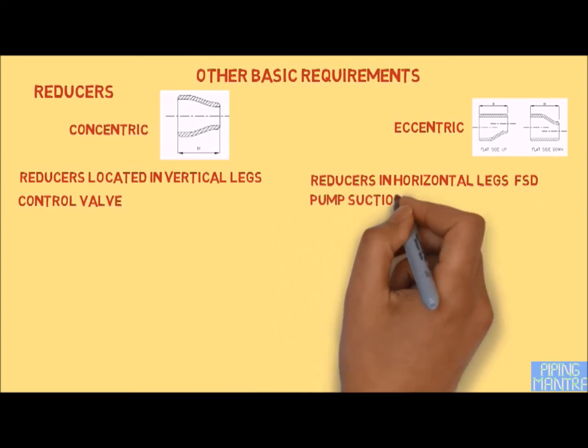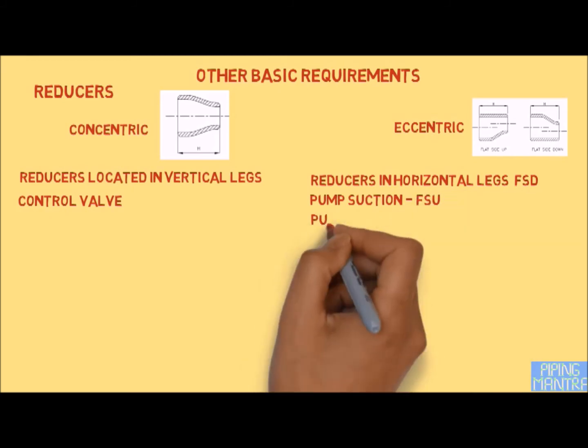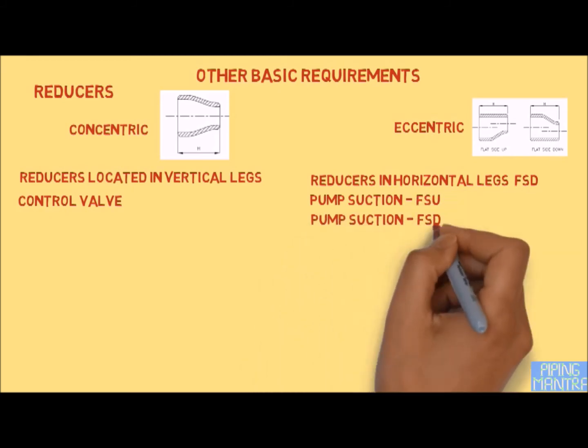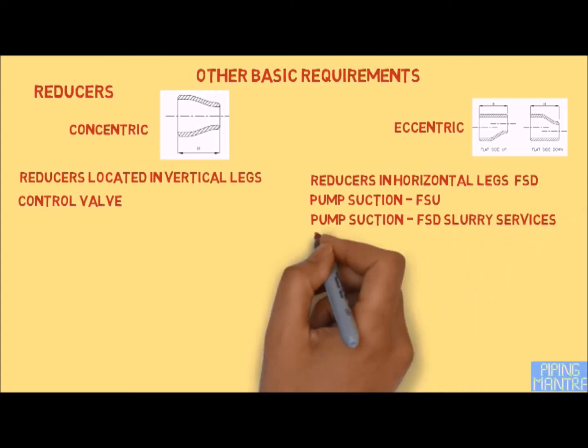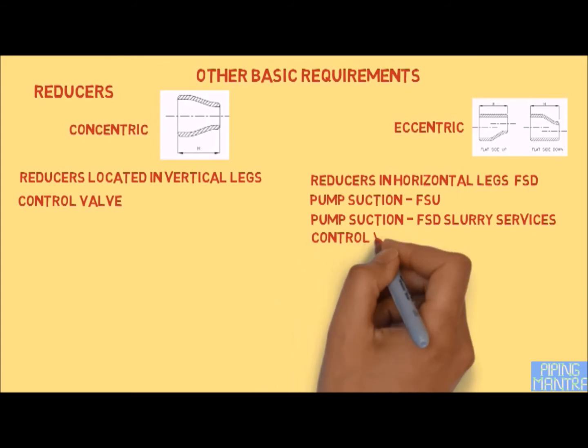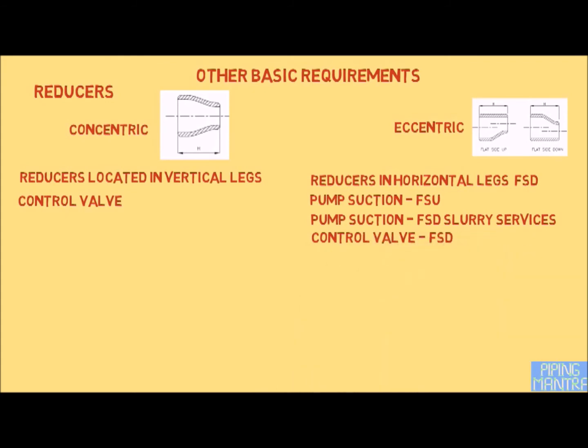For all pump suction lines, we use a flat side up reducer — this is a question commonly asked in piping interviews. For pump suction lines carrying slurry fluid, we use a flat side down eccentric reducer. Similarly, for control valves, normally all control valves use flat side down.